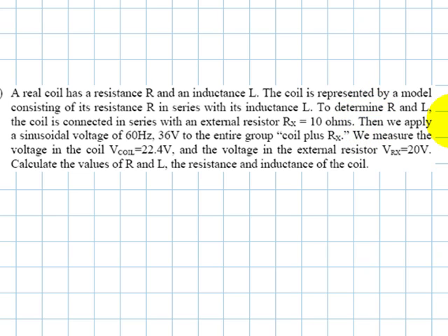Then we apply a sinusoidal voltage of 60 Hz, 36 volts to the entire group coil plus Rx. We measure the voltage of the coil, 22.4 volts.